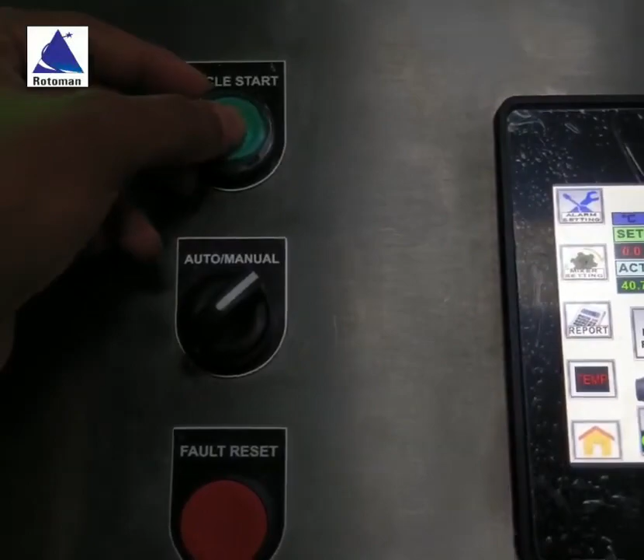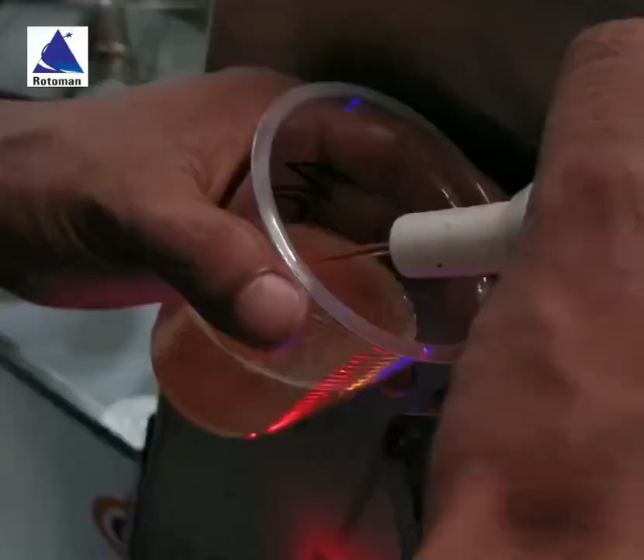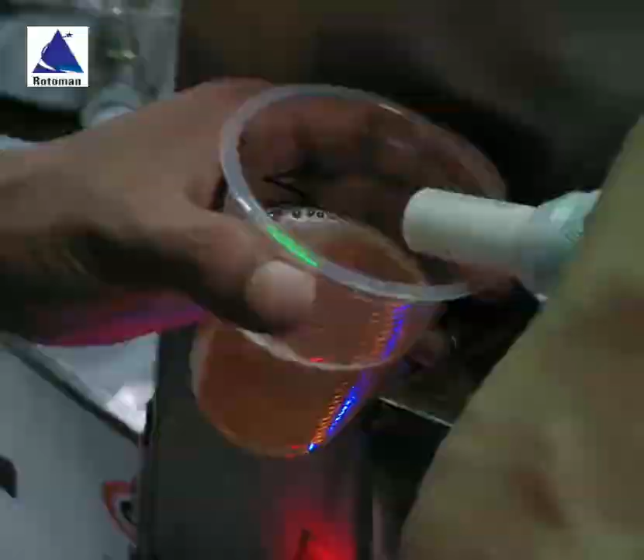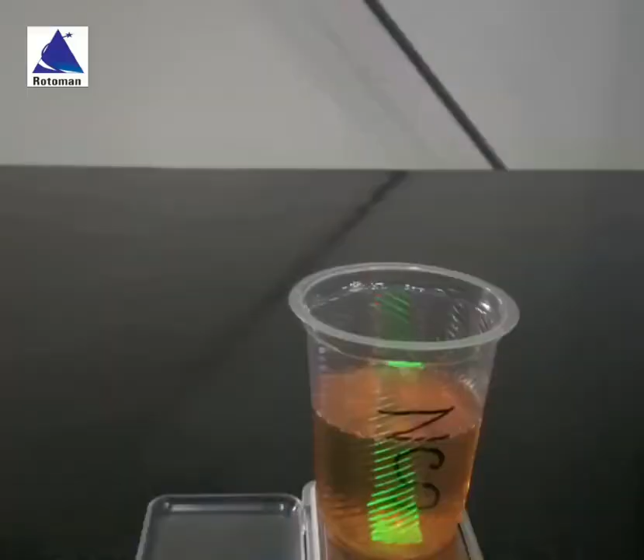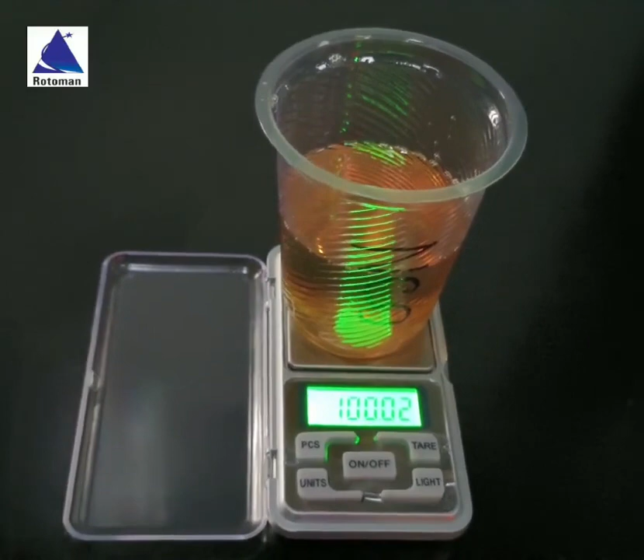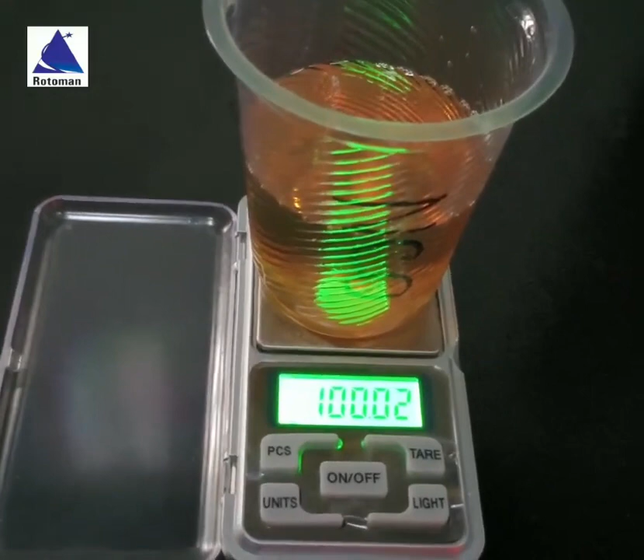Press the cycle start push button from the operating screen to take the NCO adhesive as shown. After the calibration procedure, we have taken the NCO adhesive and noted down the value. The set was 100 and what we have measured is 100.02. So almost very accurate. This completes the calibration procedure of NCO.